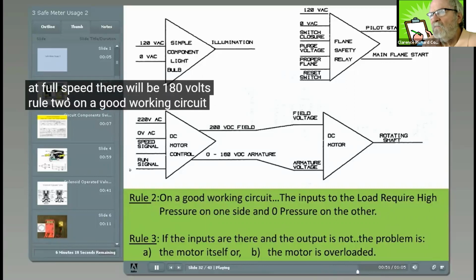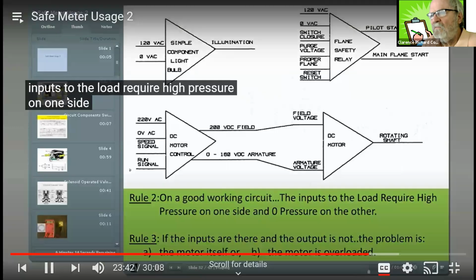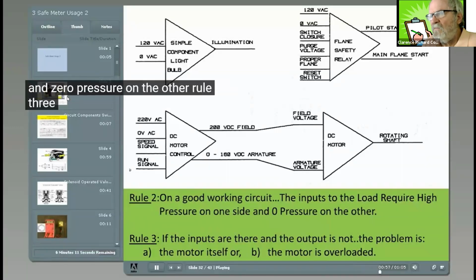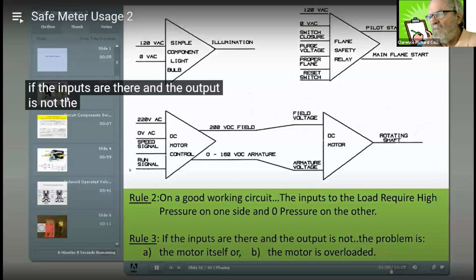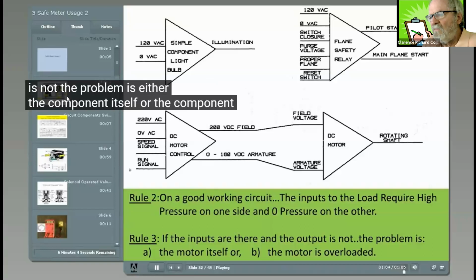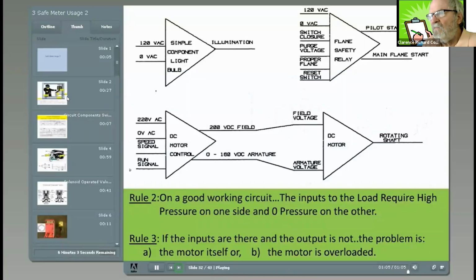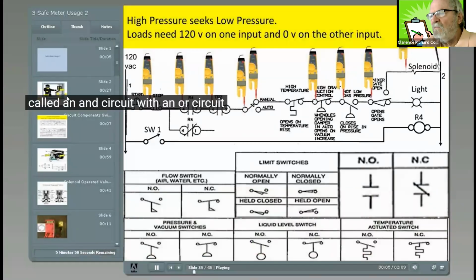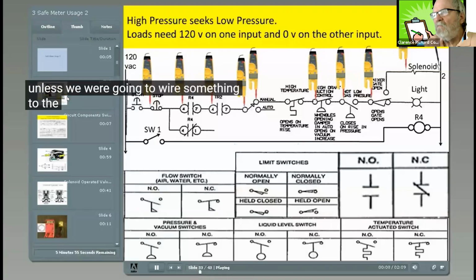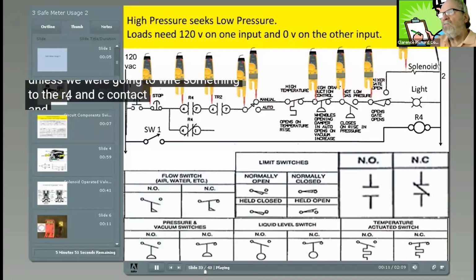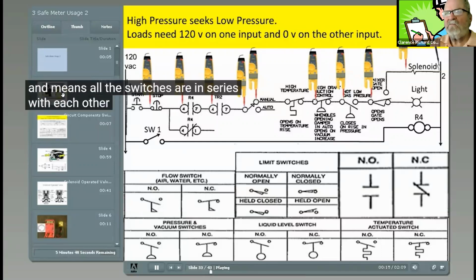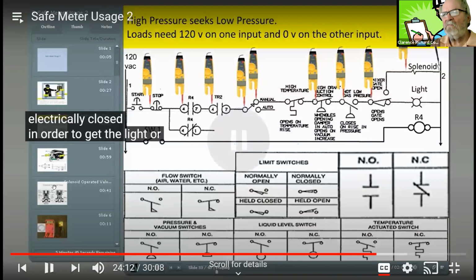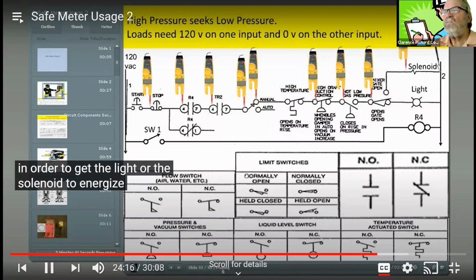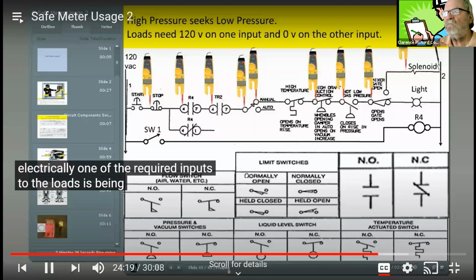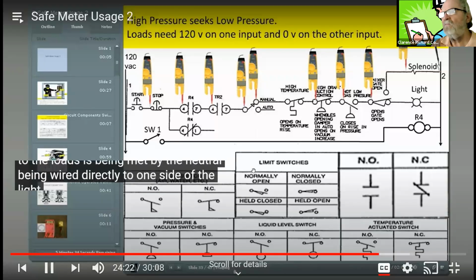Rule 2. On a good working circuit, the inputs to the load require high pressure on one side and 0 pressure on the other. Rule 3. If the inputs are there and the output is not, the problem is either the component itself or the component is overloaded. Called an AND circuit with an OR circuit at the tail end, unless we were going to wire something to the R4 and C contact. AND means all the switches are in series with each other, and they have to be electrically closed in order to get the light, or the solenoid to energize. Electrically, one of the required inputs to the loads is being met by the neutral being wired directly to one side of the light and solenoid.